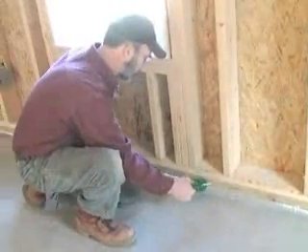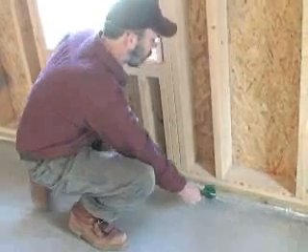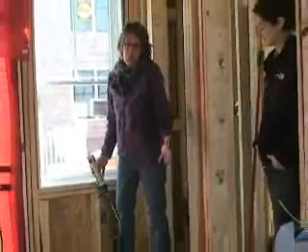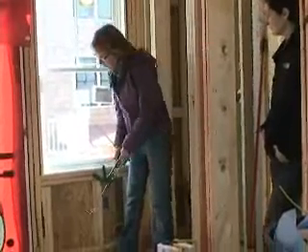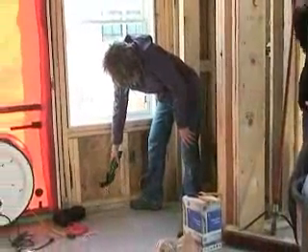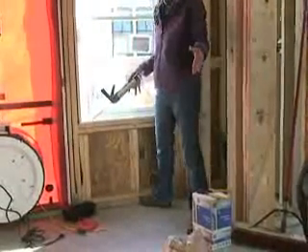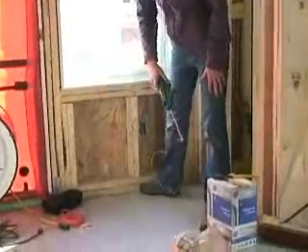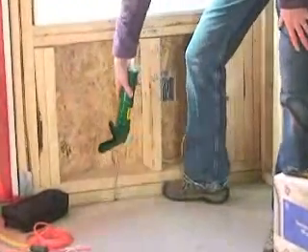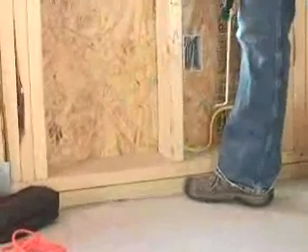Fiberglass lets air move through, and that's what we're trying to eliminate — air moving through, air equals heat, or even water moving through buildings, which we don't want to see. Another insulation detail that we always try to do is under the slabs. This is a slab on grade construction. Here we have one inch of rigid under the slab, and the detail is that it wraps up here, so it kind of isolates the slab. If you don't do that, there's a huge heat loss through the edge where this is sitting on concrete. This stops the heat from going out, so it's an important detail.